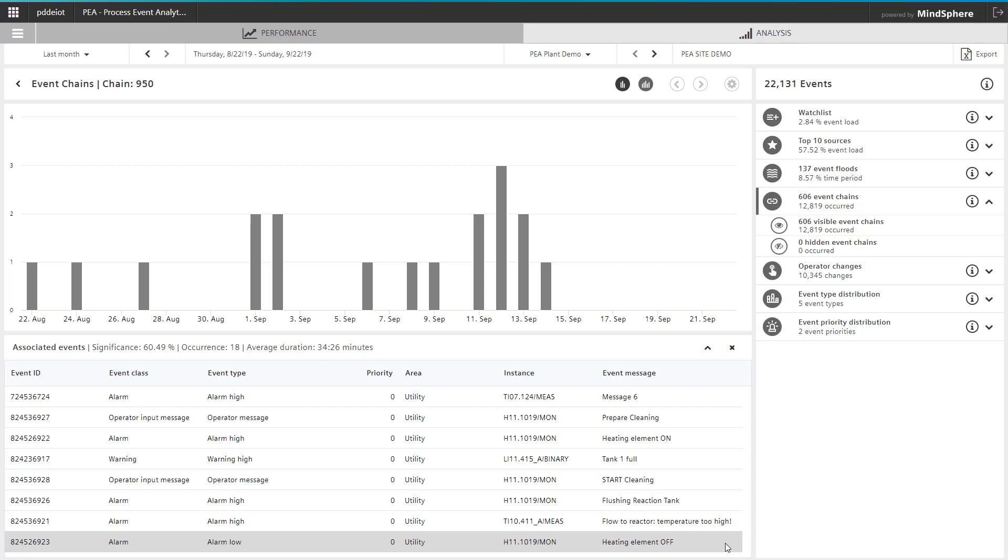Process event analytics detects this chain, including the frequency. Optimizing this chain's number of alarms by silencing those that are unnecessary will reduce the workload of the operating personnel.